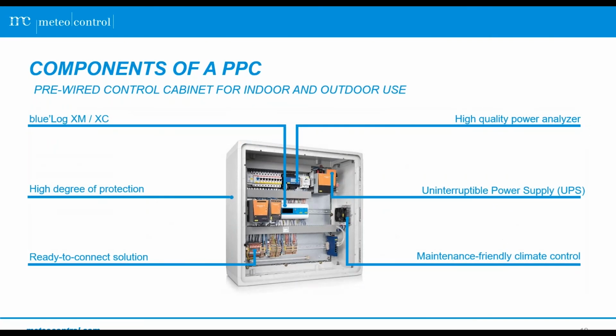As we said before, we can provide a full system with stations and accessories, or integrate the Bluelog as a slave, for example, in an existing SCADA. We had a case of an external SCADA system where we needed to use the Bluelog because it allows not having to develop the compatibility to the inverters. You can integrate it via TCP/IP communication and send the data to other systems, have the local SCADA and send the data separately to another system.